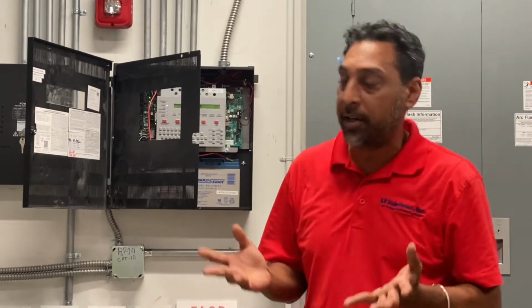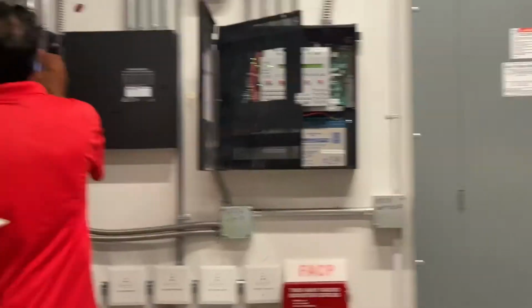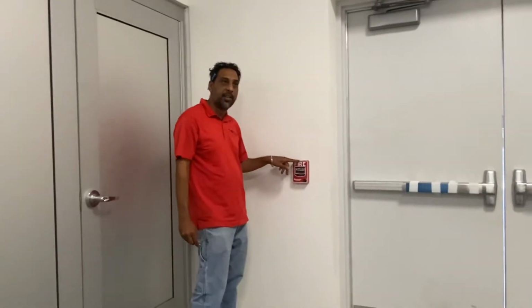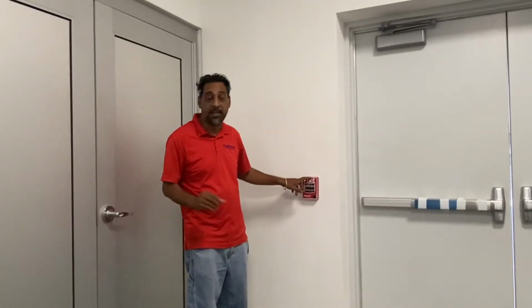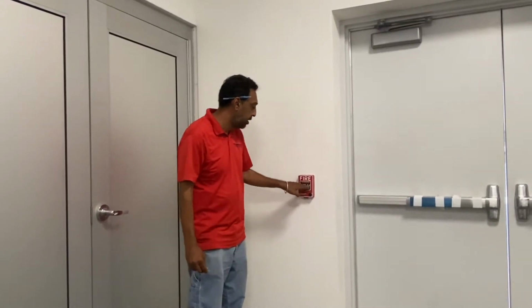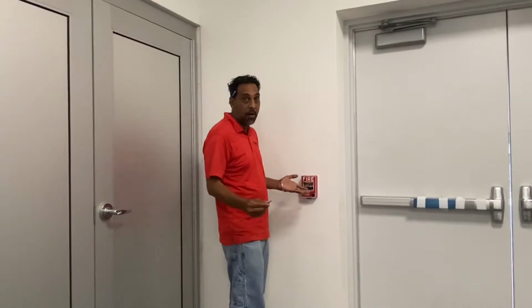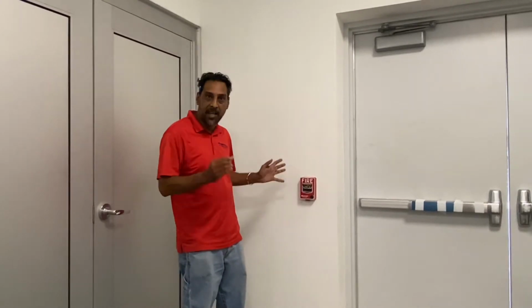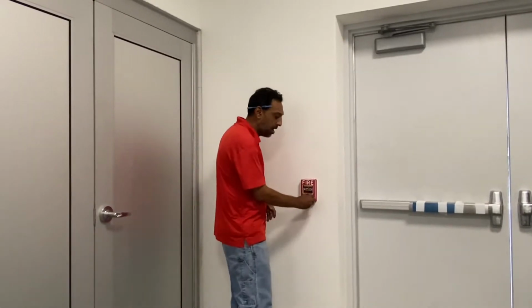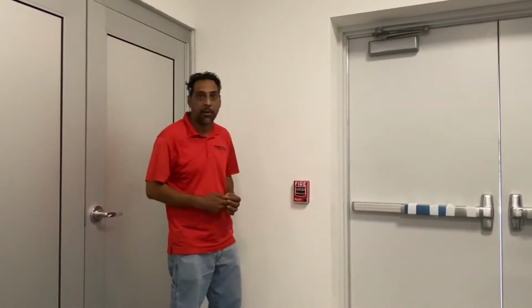Pull stations, I want to show you guys how to activate. You have the pull stations right here. As you see here, this says 1M17 on it. It's fully addressable. I'll show you guys the description. So when you want to activate, you push in, you pull down. And now your fire alarm's going off. Now, before you can reset that, once you see it's a pull station, you need to come here, open the door, close it. That's how you reset this pull station. So see, you pulled it back up, so then now you can walk back in here.